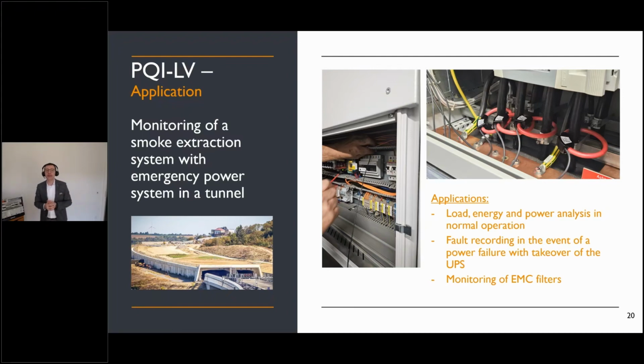Inside this tunnel, there is a smoke extraction system with an emergency power system. The smoke extraction system is using a frequency inverter to be flexible enough to bring the smoke out of the tunnel in a really fast way in case of a fire. And there you can see the flexibility of these devices. The device is installed for normal application, load, energy, and power analysis in normal operation. If a fault happens, in case of a power failure as well as in case of a fire, the system is triggered, and then we can see directly the UPS system and maybe see what's happening in that situation. If there is an issue with it, you can directly react on that issue.